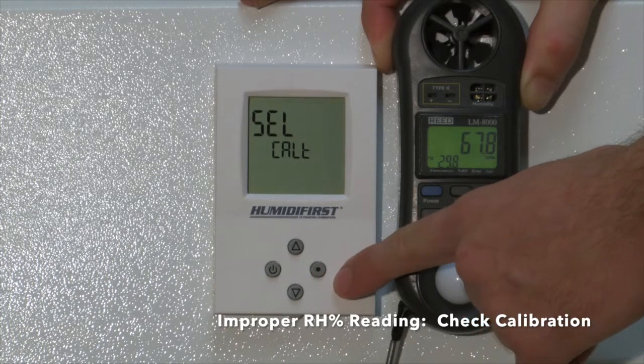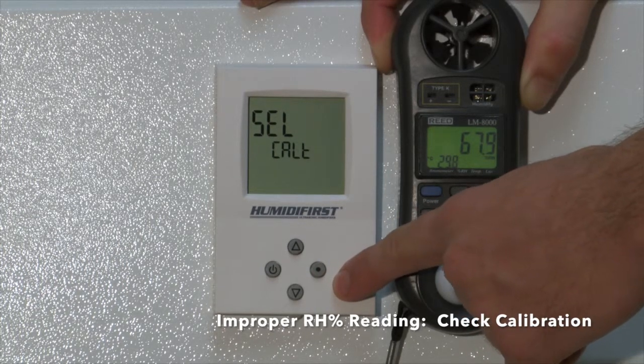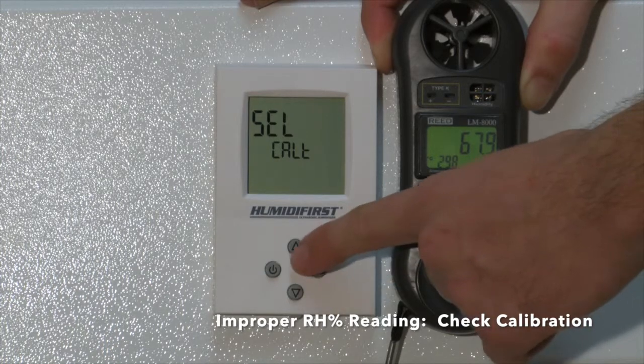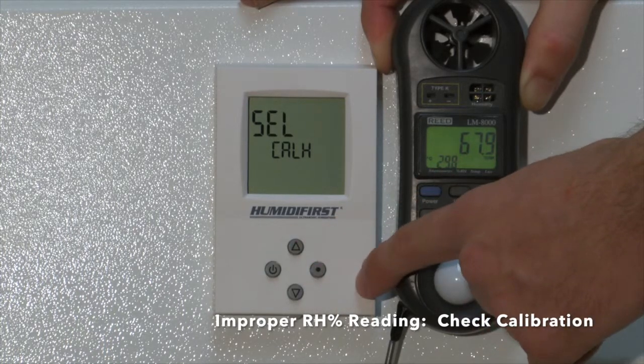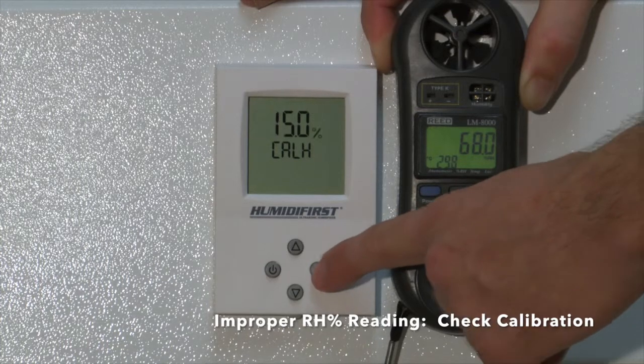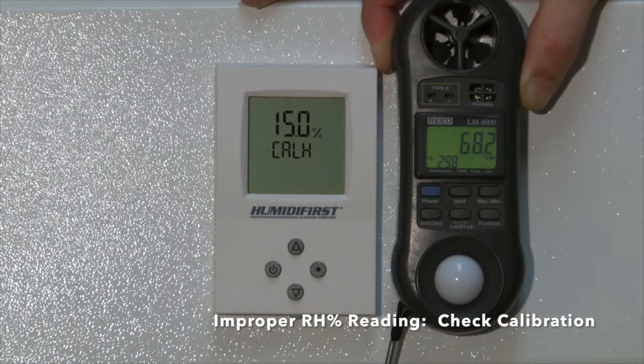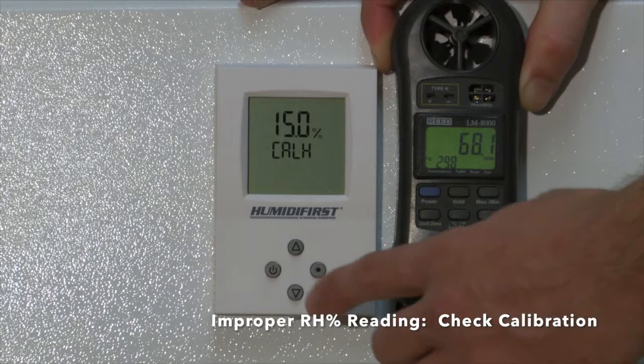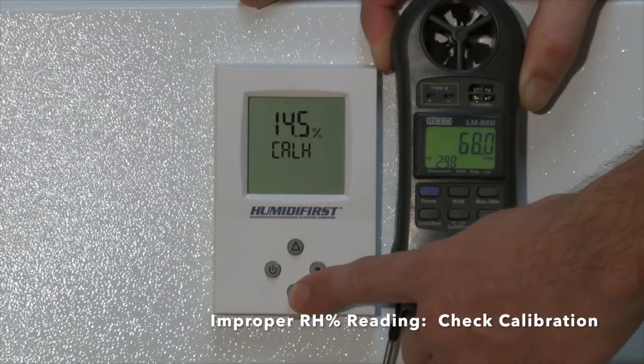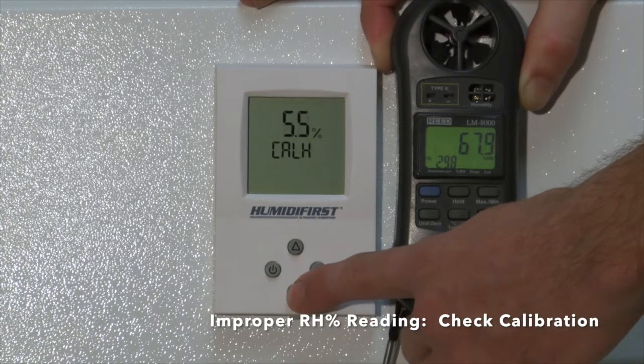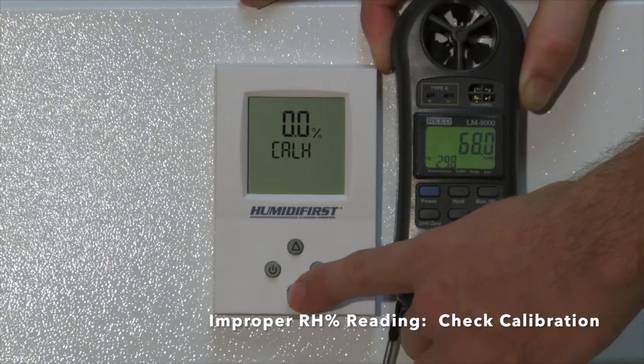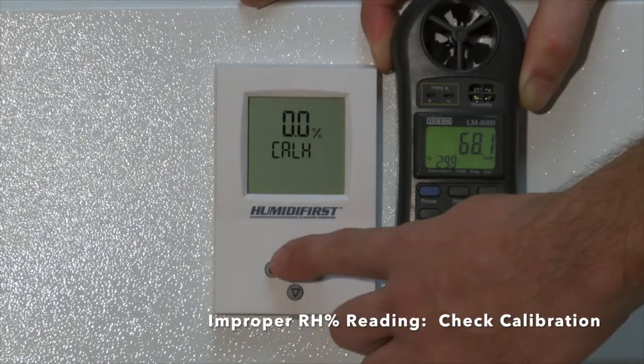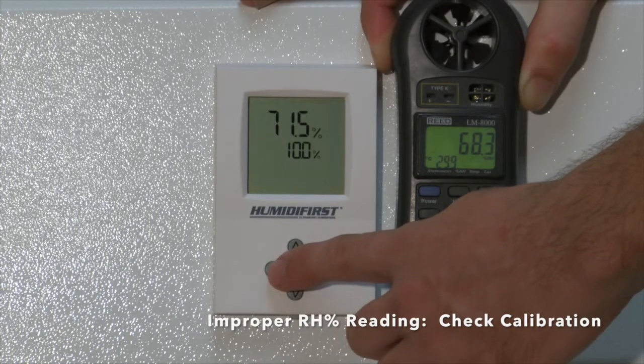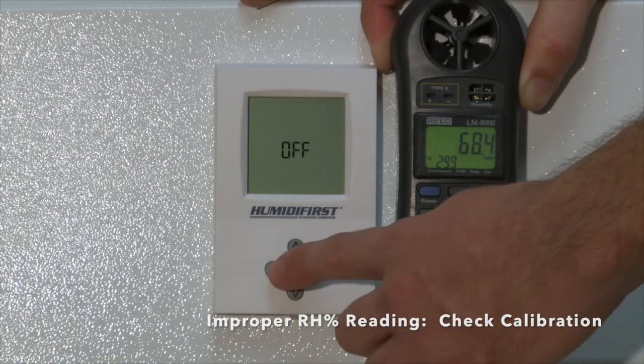and you will see SELCALT, that's Select Calibrate Temperature. If you hit up, it'll say Select Calibrate Humidity. Press the dot button. Right now it is set at 15%. This means the humidistat will read 15% above its measure. Again, a humidistat should always be calibrated to 0%. Once calibrated, press the power button 3 times to reset the humidistat.